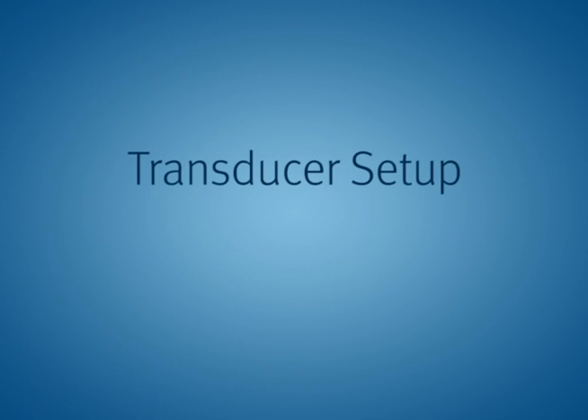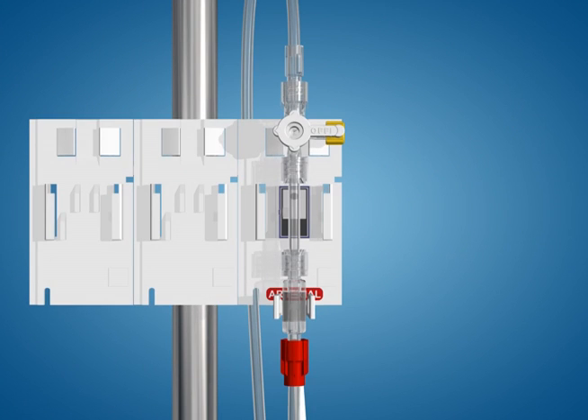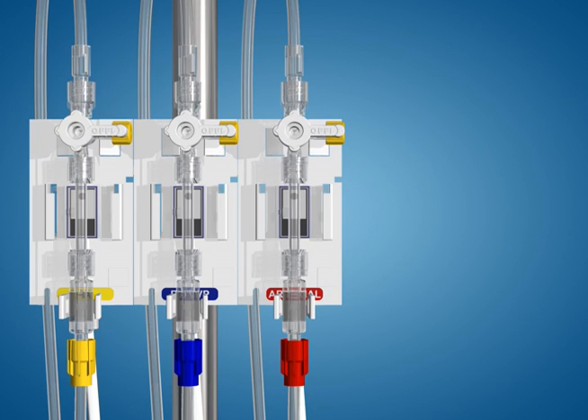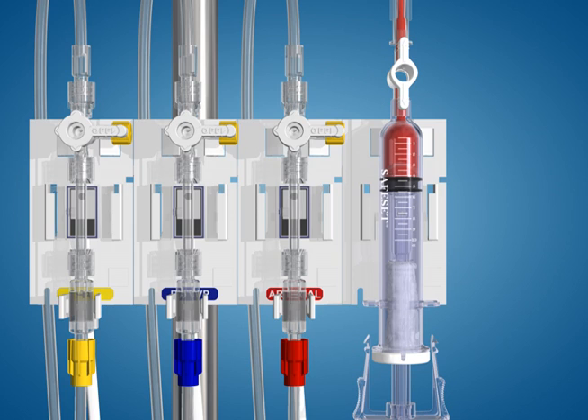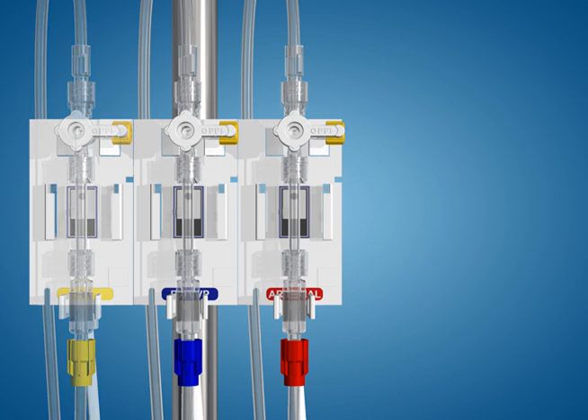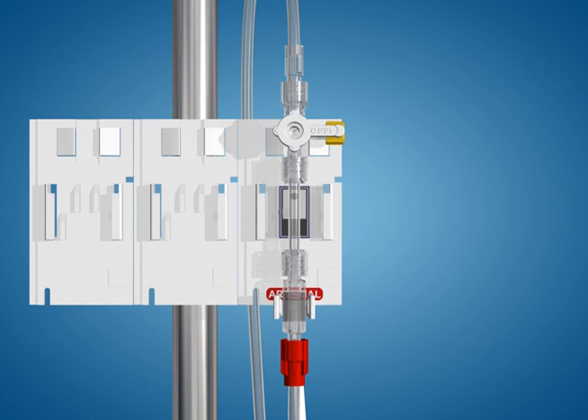Transducer setup. ICU Medical offers standard Transpac transducer kits in single, double, and triple line options. ICU Medical also offers the Transpac transducer system with the SafeSet blood sampling system to reduce blood waste and increase the efficiency of the blood sampling process. In this example, we will only be monitoring arterial pressure and will be using a single-line Transpac kit.